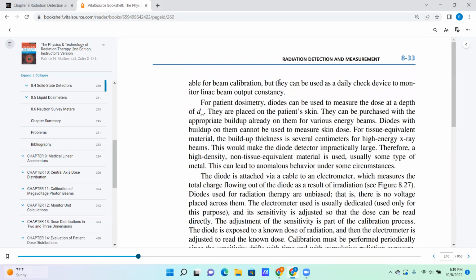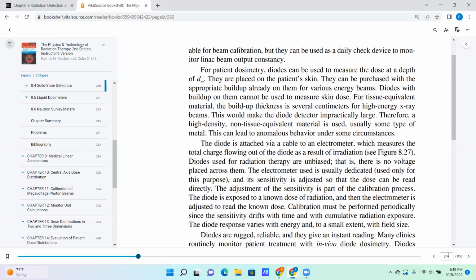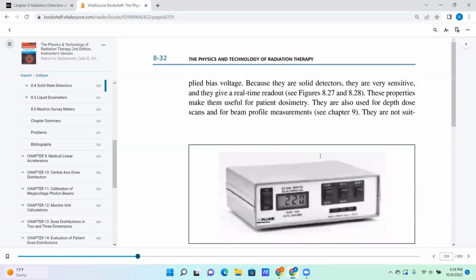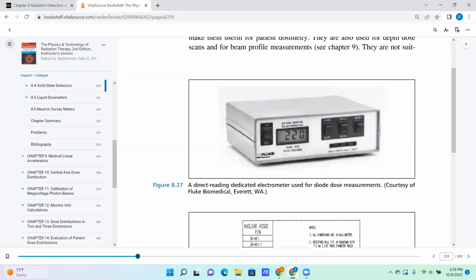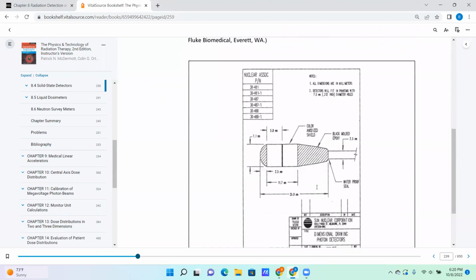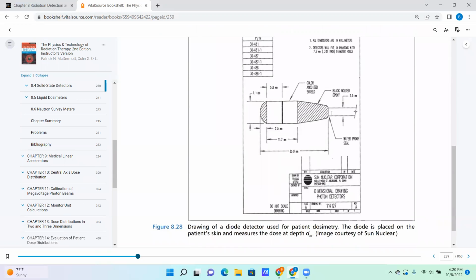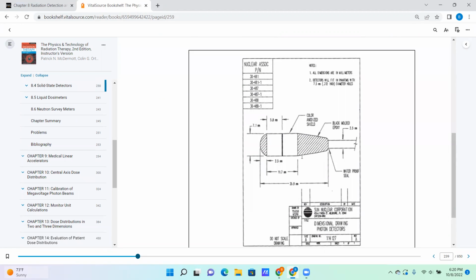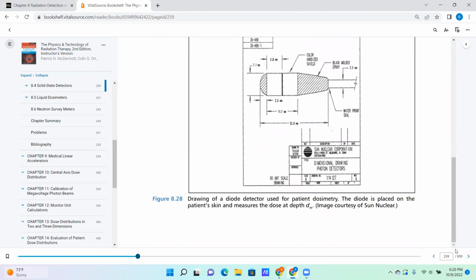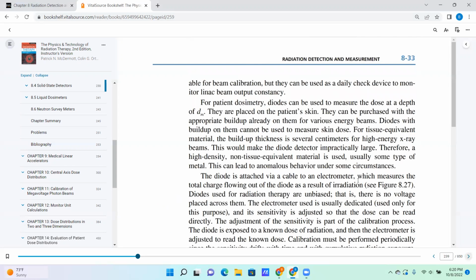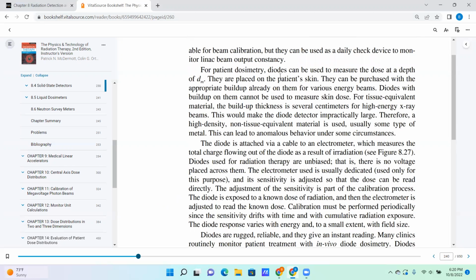They're not suitable for beam calibration, but they can be used as a daily check device to monitor LINAC beam output consistency. So let's go back and take a look at these pictures here. This is a direct reading dedicated electrometer used for diode dose measurements. And you've got a drawing of a diode detector used for patient dosimetry. The diode is placed on the patient's skin and measures the dose at depth D max. So you place these on patient skin.